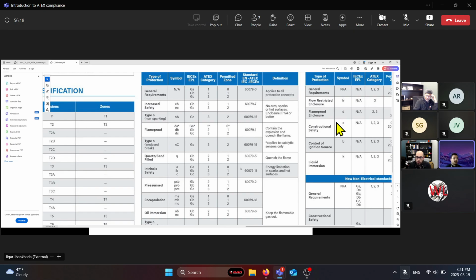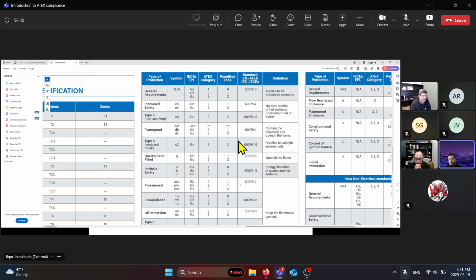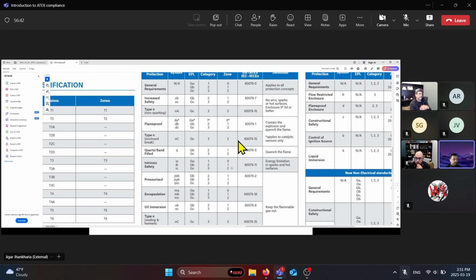And they basically define intrinsic safety as an energy limitation in sparks and hot surfaces, where you use intrinsically safe barriers in the product as well, and design it according to the standard with various creepage and clearances on your PCB or any electricals that are inside the product. So for zone 0, that's one method of protection you can achieve. Zone 1 as well, zone 2.